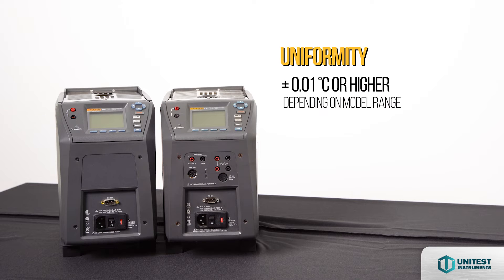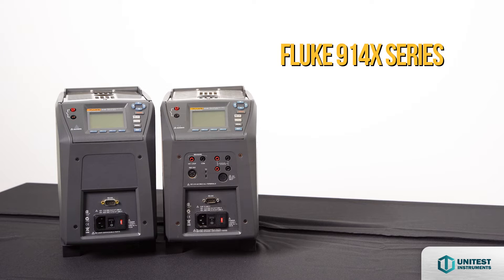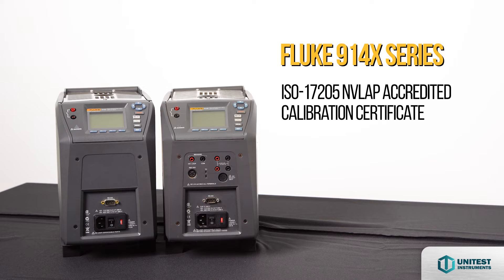Uniformity plus or minus 0.01 degrees Celsius or better. Immersion depth 150mm or 6 inches. The Fluke 914X comes with an NVLAP accredited calibration certificate with a 1-year warranty.